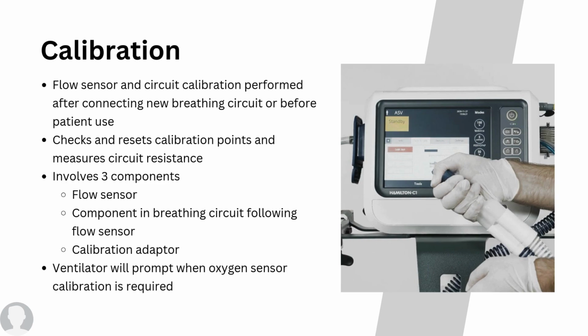The calibration involves three components: the flow sensor, the component in breathing circuit following the flow sensor, and the calibration adapter. The ventilator will prompt when an oxygen sensor calibration is required, in which it's exposed to room air and 100% oxygen for proper calibration.